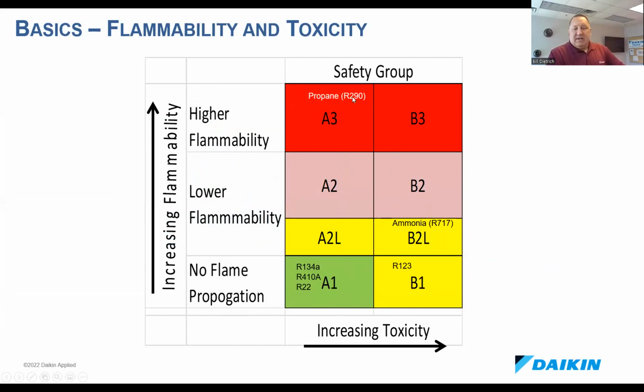Propane, it's actually a pretty good refrigerant. Isobutane is another one. And there's going to be a lot of use for them, but there'll be strict limits on how much charge can be in the system. But we'll see propane and isobutane in vending machines, refrigerators, things like that. And then you've got ammonia. Ammonia is slightly flammable, but it's got a higher toxicity, so it falls into that B2L category.